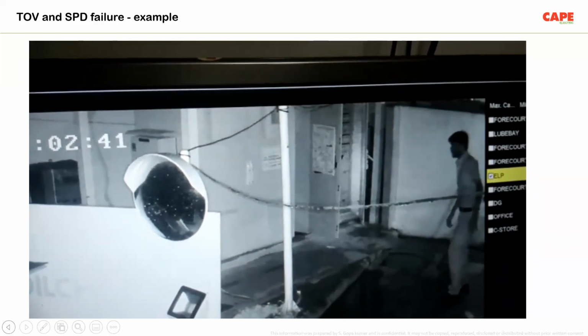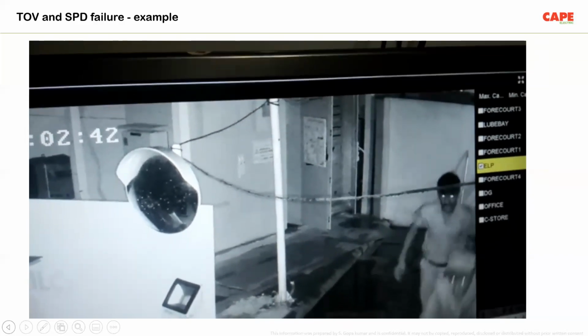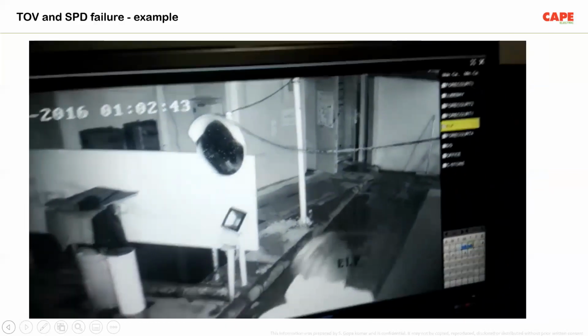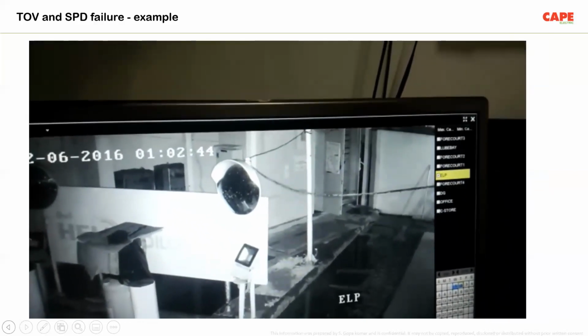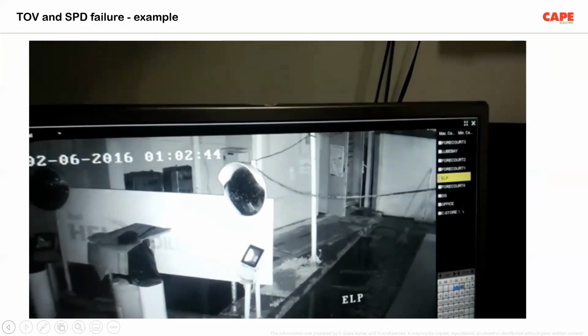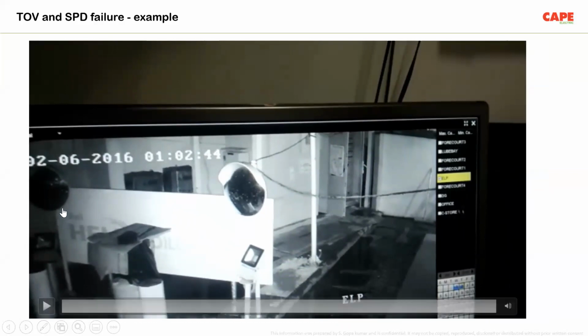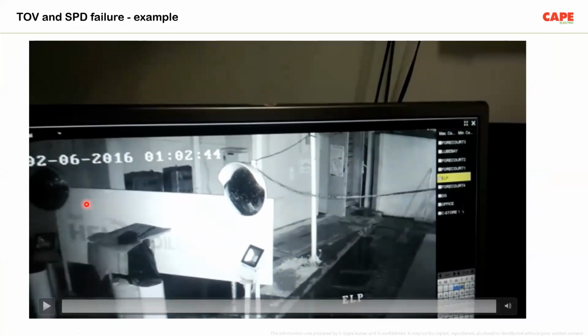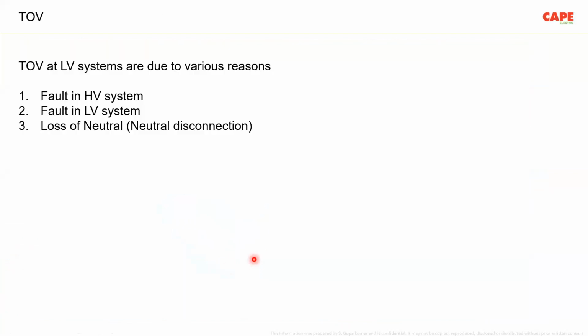What has exploded in this panel board is an SPD, surge protective device. The SPD which is installed inside has burned. It's at a petrol pump, not a normal place, and you can also see a little bit of where it is installed in this particular video. You can look at this place, so you will understand which company it is. So what has happened is the explosion of an SPD.